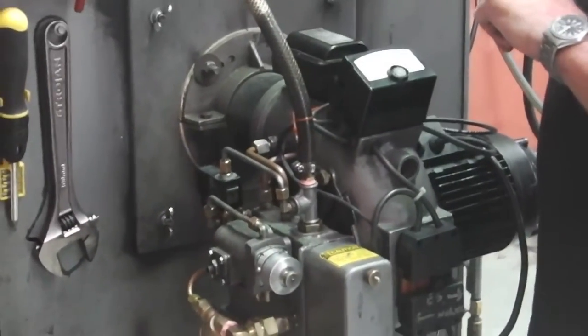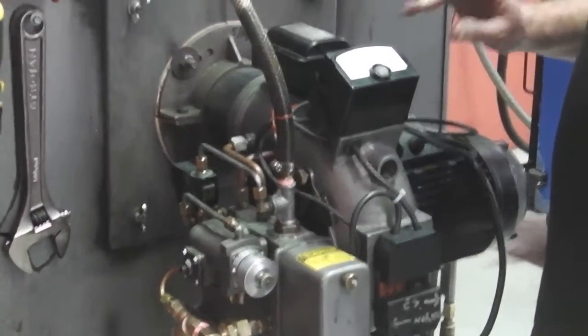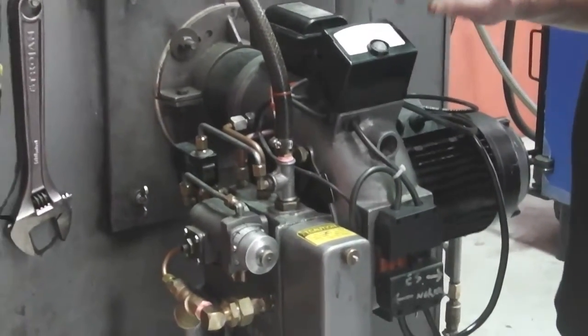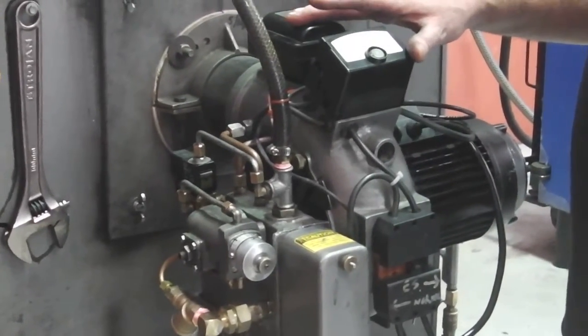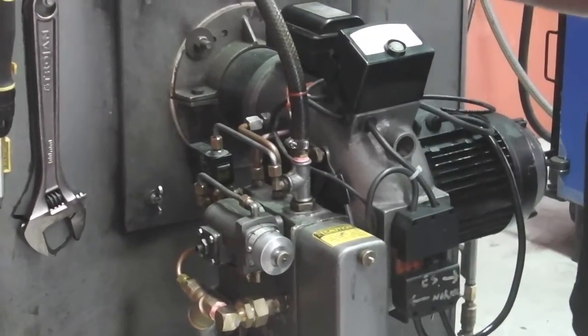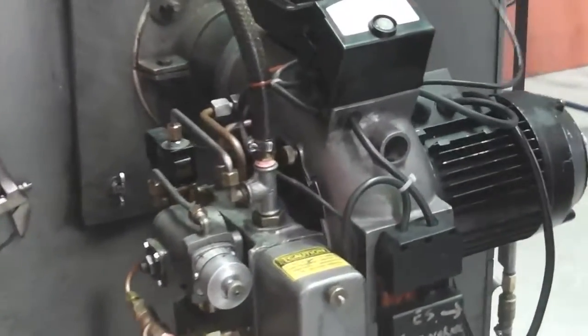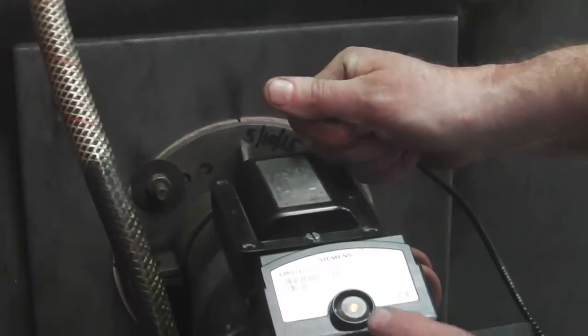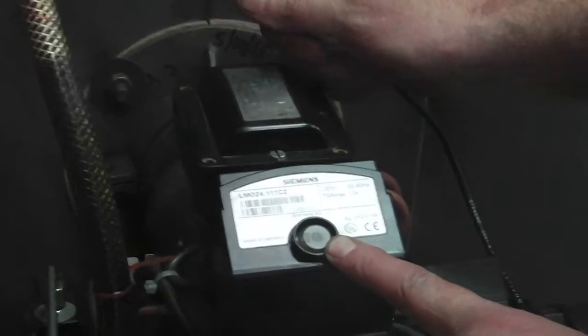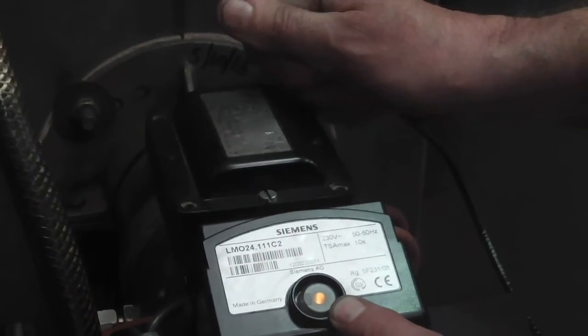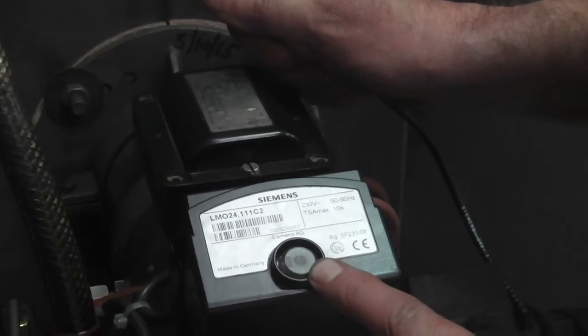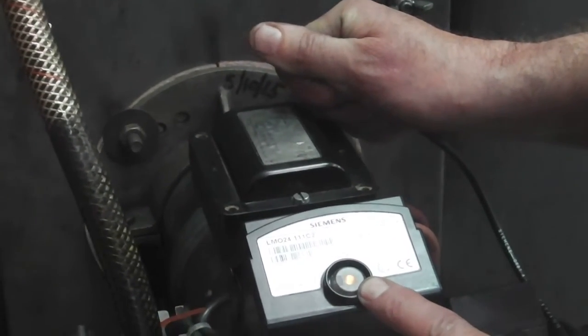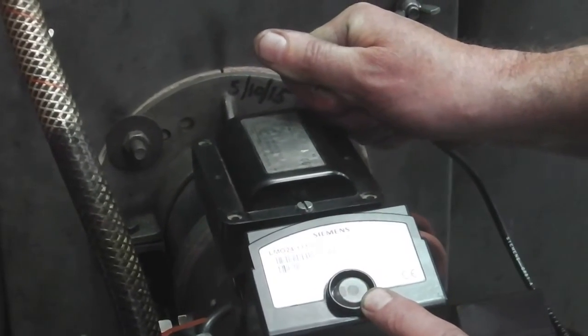Just one very brief thing at the end, all burner guns of this style have a safety sensor or PE cell, photoelectric cell. If I remove the photoelectric cell from the side here, the burner gun shuts the oil supply down, and will eventually go into a red or flame fail situation. This is by design and for safety reasons.